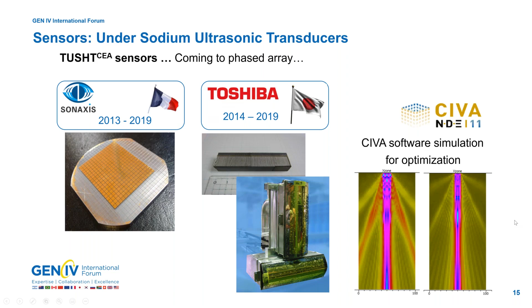And developing that sensors, we are using the CIVA software. CIVA is a software which is widely spread all around the world in the industry, and that will help for designing and optimizing the sensors because we can simulate any kind of piezoelectrical sensor, and it's very efficient to check that we are able to focus at the right distance. You see here in light blue, it corresponds to the place where all the elements located here can be focused to get a high energy and so a high echo response. I am moving to the next slide.